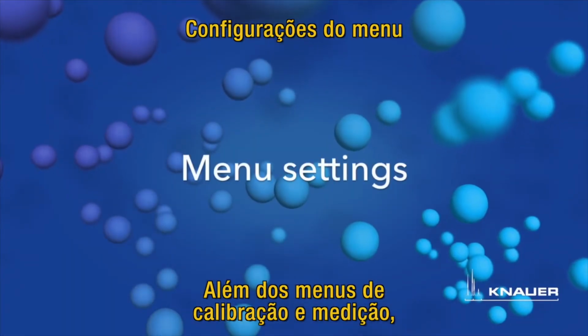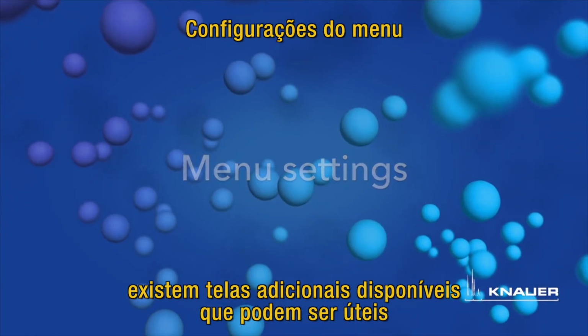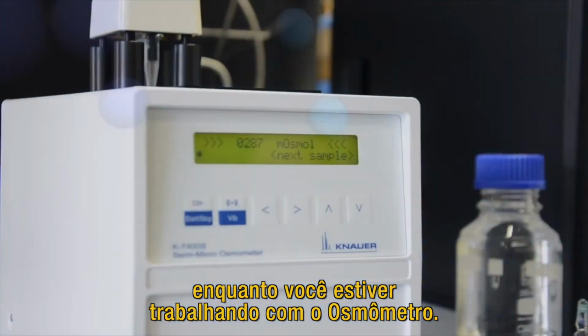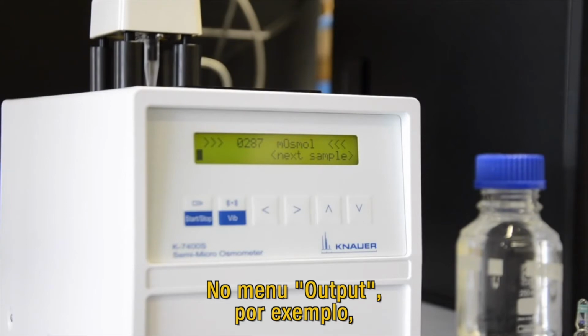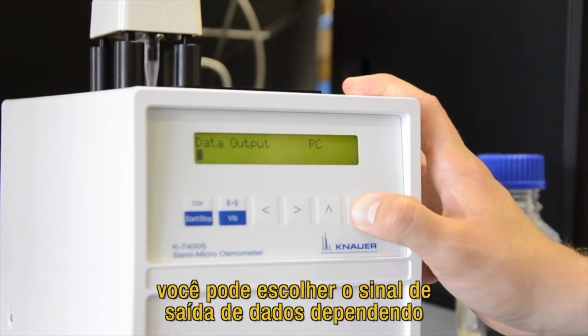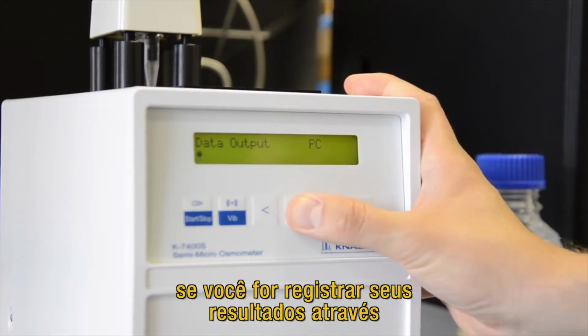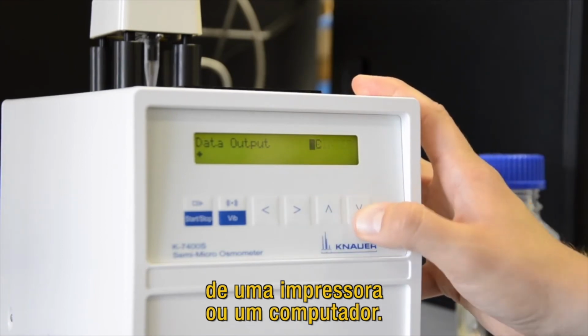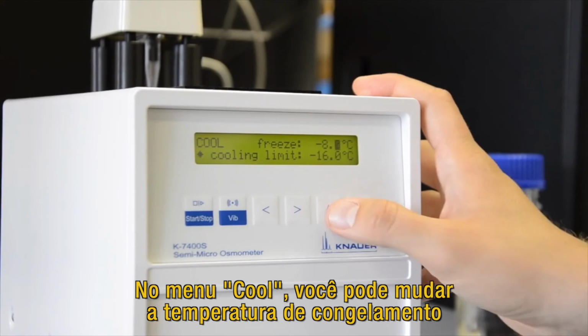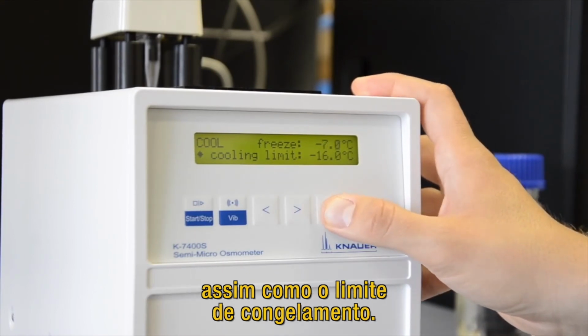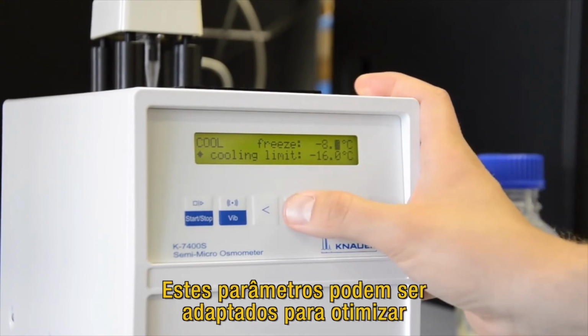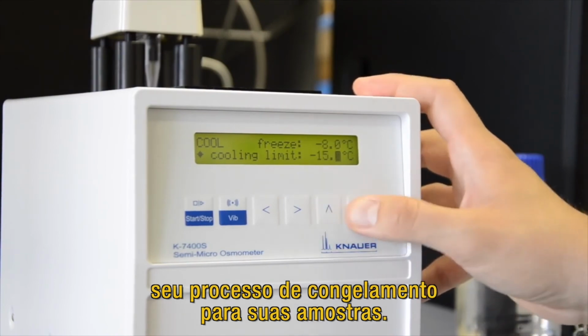Apart from the calibration and the measurement menu, there are additional screens available that can be useful while working with the osmometer. In the output menu, for example, you can choose the output signal depending on if you use a printer or a computer to record your results. In the cool menu, you can change the freezing temperature as well as the freezing limit. Both parameters can be adapted to optimize the freezing process for your samples.